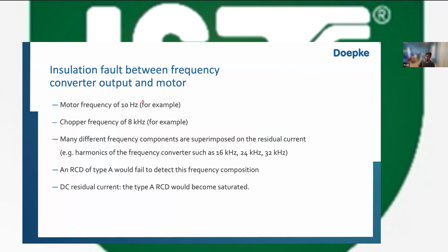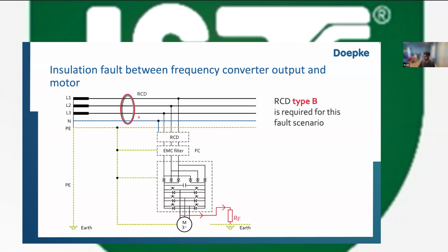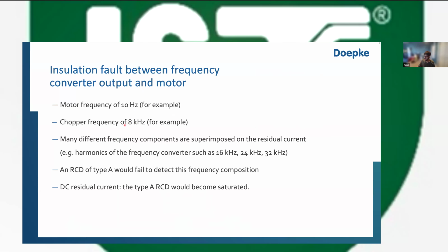Important thing I want to explain here is that if you have a fault between the frequency converter's output and the motor, the motor's frequency is say 10 hertz. But very importantly, the chopper, which is these IGBTs here, may be operating at a frequency of 8 kilohertz to generate this 10 hertz frequency. As a result, the actual fault current will look like there are different frequencies superimposed on the residual current. So we may have 16 kilohertz, 24 kilohertz, 32 kilohertz. There are harmonics of that particular component. And even a type A would fail to detect this. Essentially what happens is that type A's core becomes saturated and it's no longer able to disconnect. So that's relatively important.